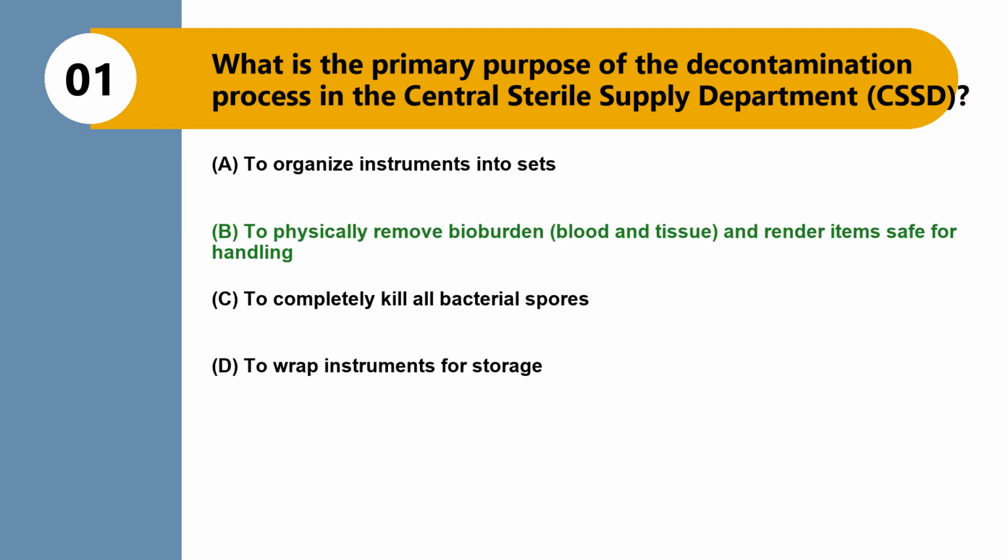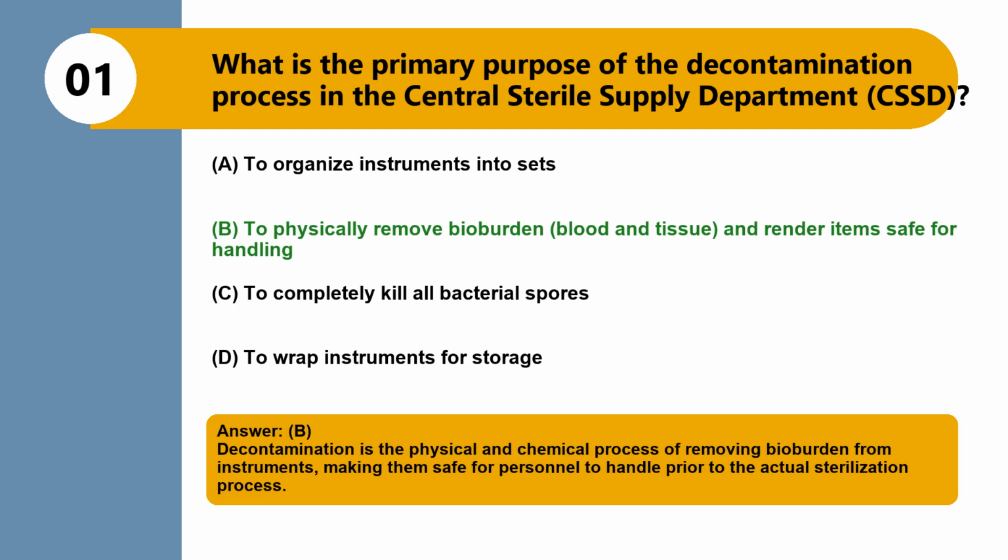The correct answer is option B. To physically remove bioburden, blood and tissue, and render items safe for handling. Decontamination is the physical and chemical process of removing bioburden from instruments, making them safe for personnel to handle prior to the actual sterilization process.